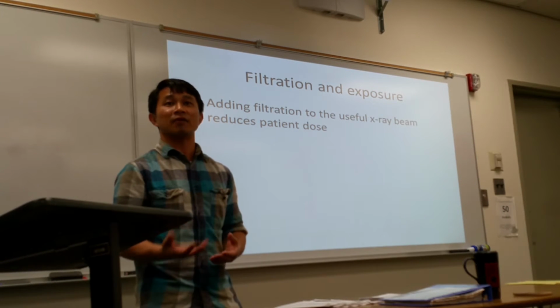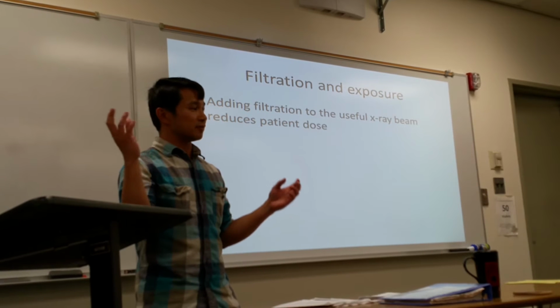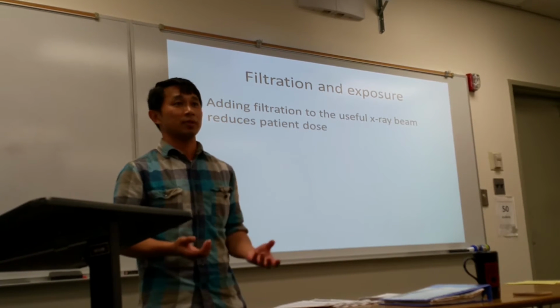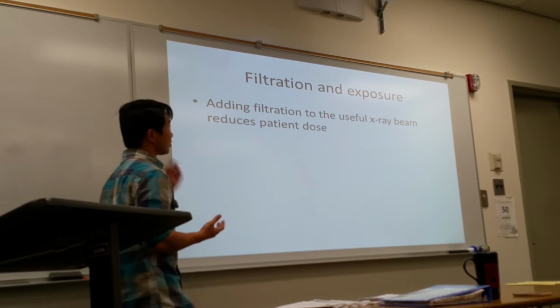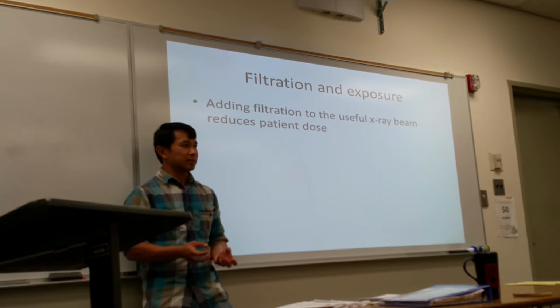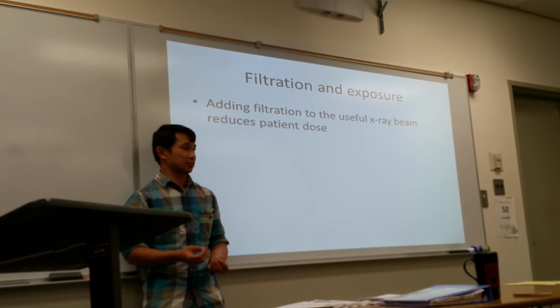That's the primary function of filtration, because it filters out all the low-level X-ray energy. Otherwise, the patient will just absorb it. The purpose of filtration is to get rid of all the beam that's not useful in diagnostic X-ray before it interacts with the patient. Therefore, patient exposure decreases.